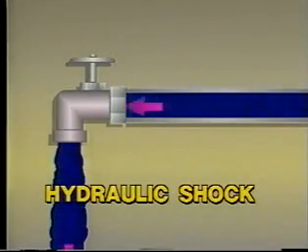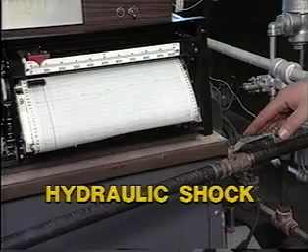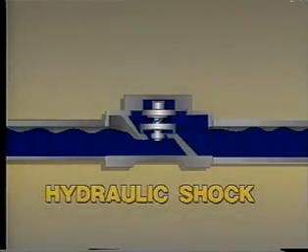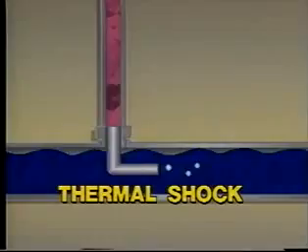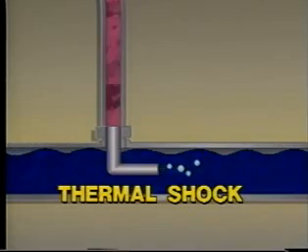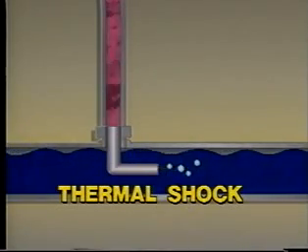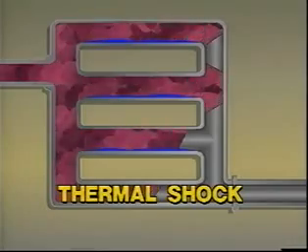Careful attention to these few guidelines will prevent most water hammer. Prevent the sudden stopping of water in pipelines by closing manual valves slowly and by installing spring-loaded center-guided silent check valves where appropriate. Prevent thermal shock by using a sparging tube wherever flash steam is discharged into condensate at a lower temperature and by ensuring that heat exchanger tubes are filled from one end.